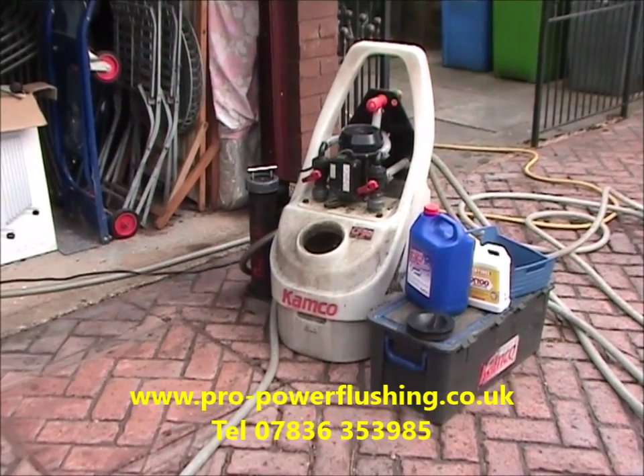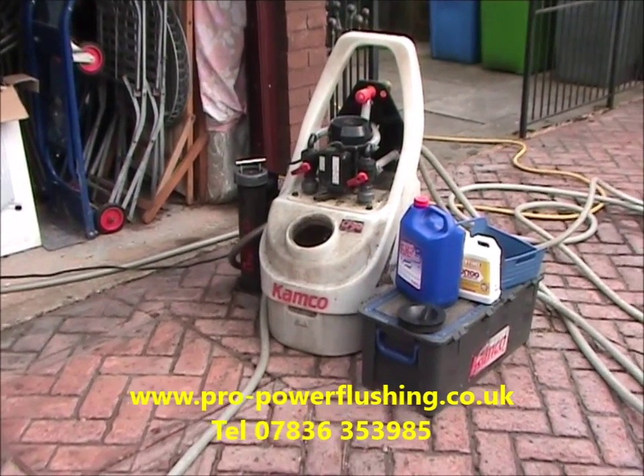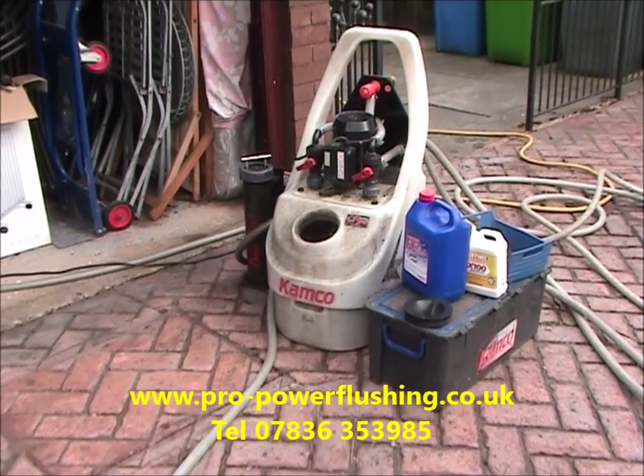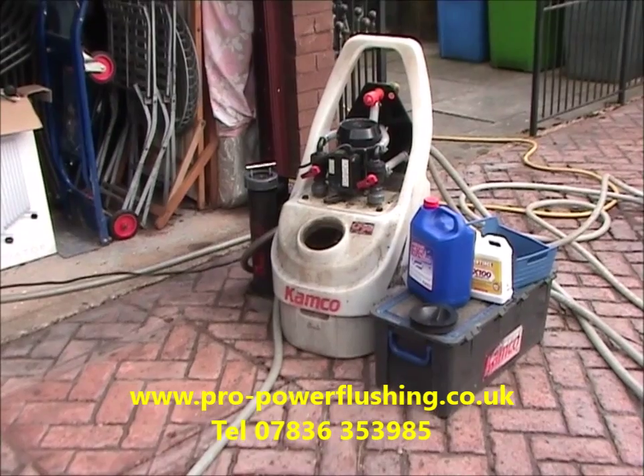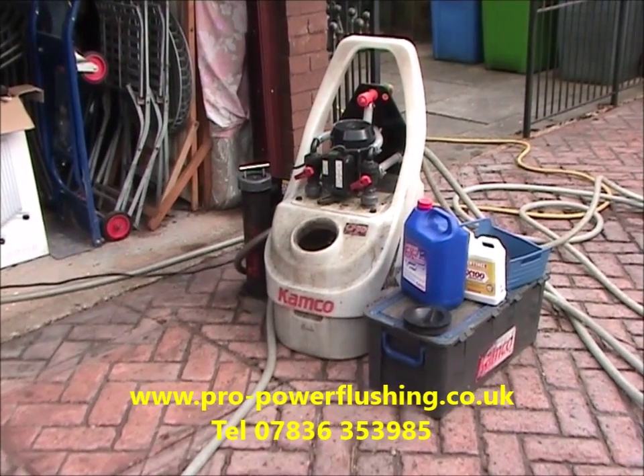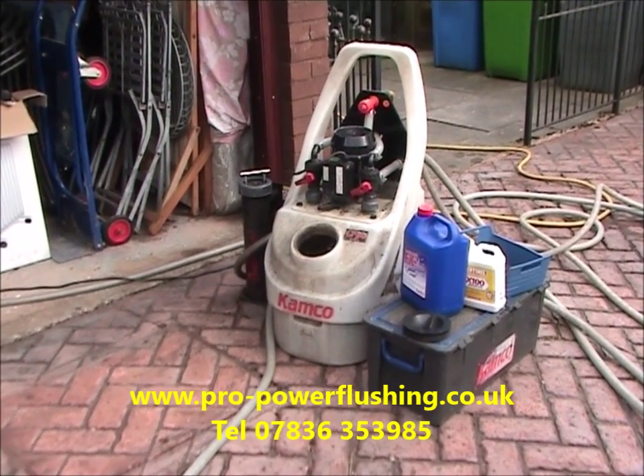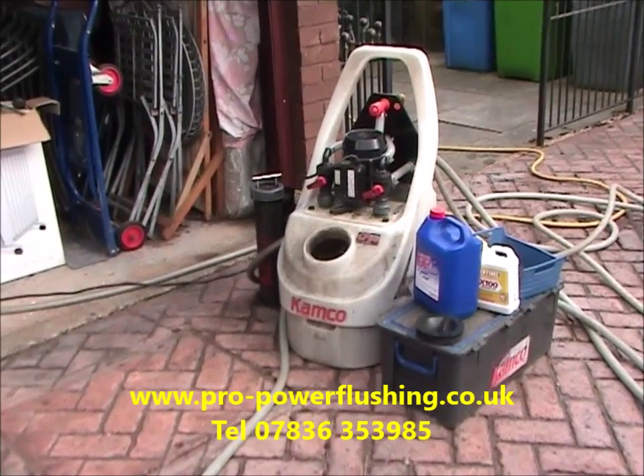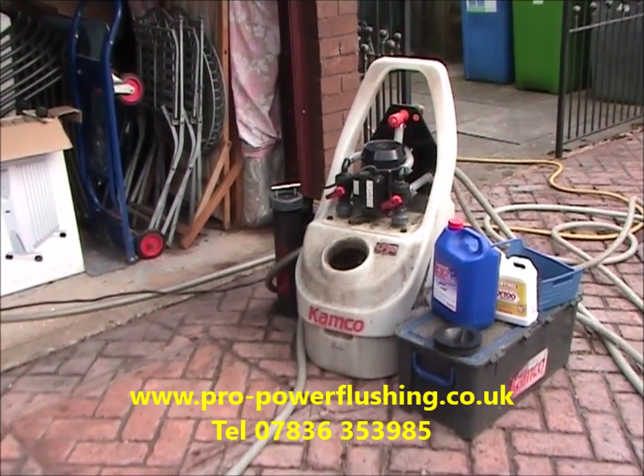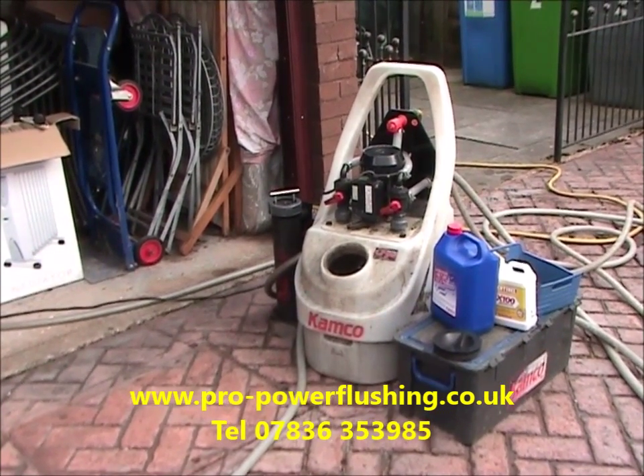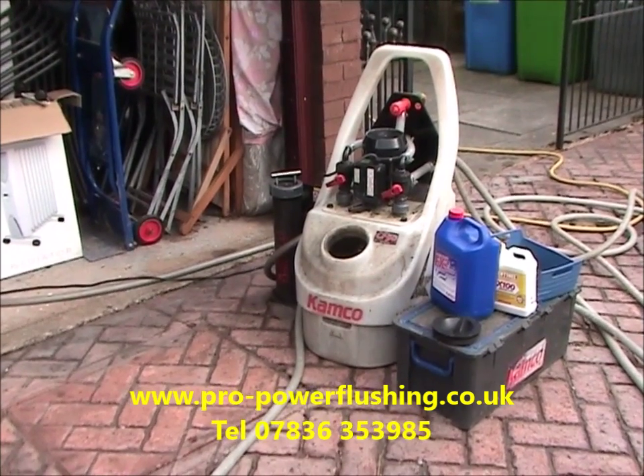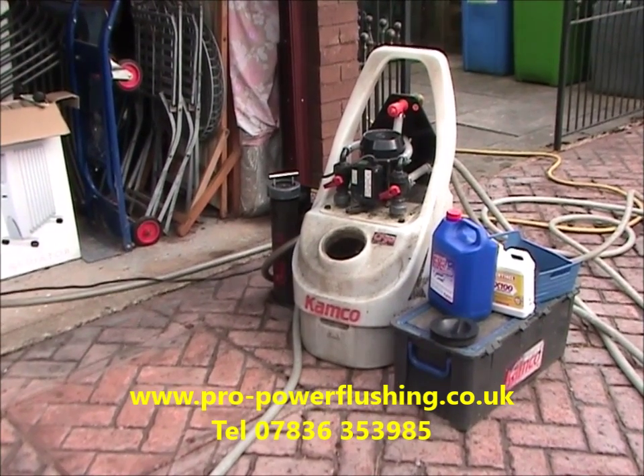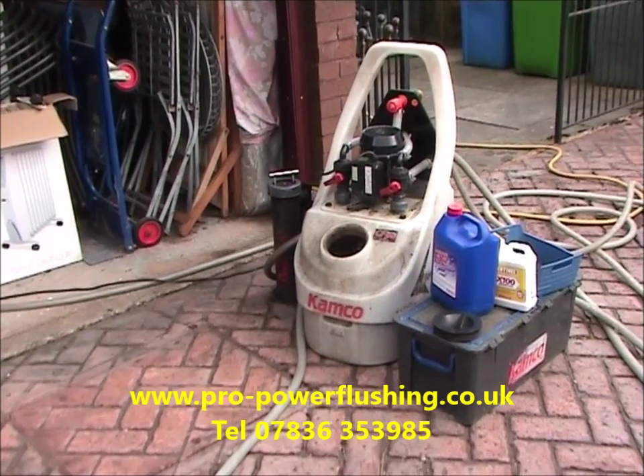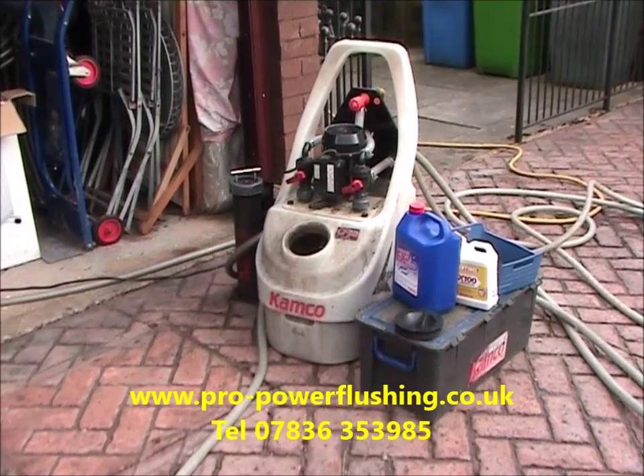It's just not worth fitting a new boiler without getting it power flushed. If the boiler breaks down in the first year or two and the manufacturer sends their engineers out and they find rust and corrosion in the system, it could actually invalidate your warranty - they could turn around and say it wasn't cleaned properly prior to the install.